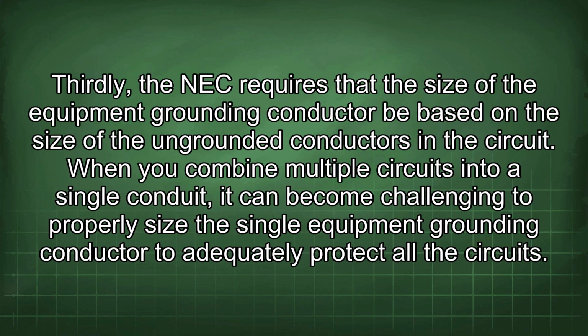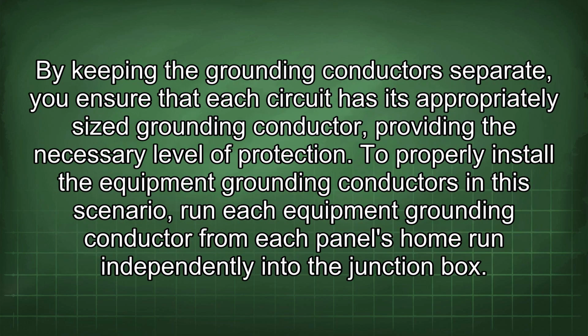Thirdly, the NEC requires that the size of the equipment grounding conductor be based on the size of the ungrounded conductors in the circuit. When you combine multiple circuits into a single conduit, it can become challenging to properly size the single equipment grounding conductor to adequately protect all the circuits. By keeping the grounding conductor separate, you ensure that each circuit has its appropriately sized grounding conductor, providing the necessary level of protection.